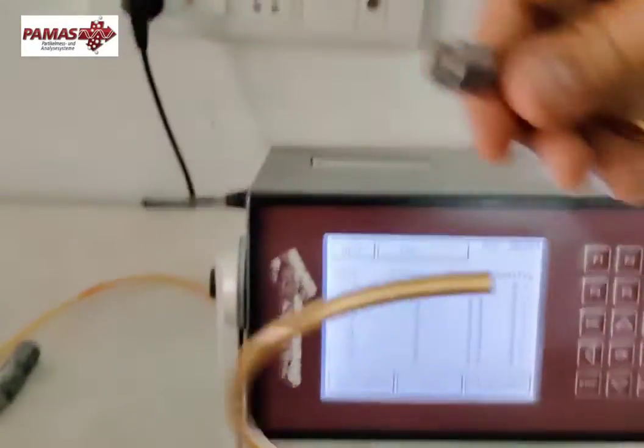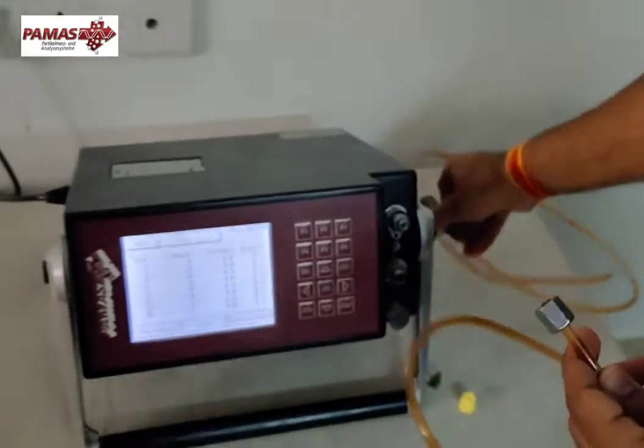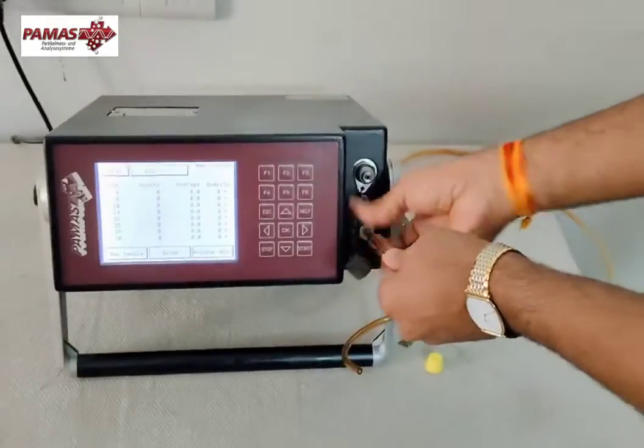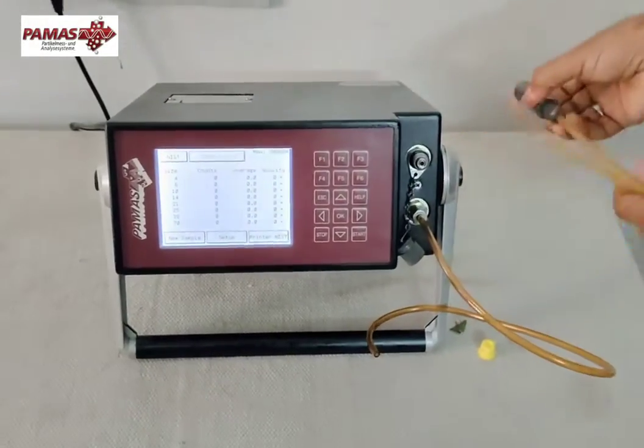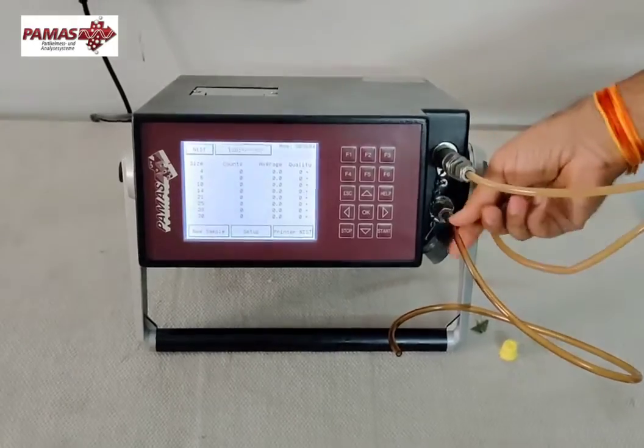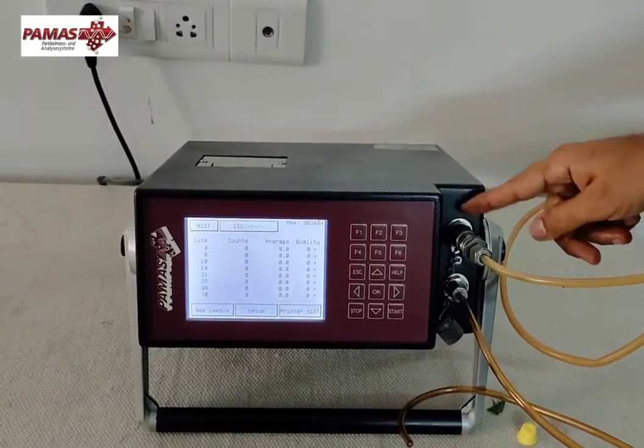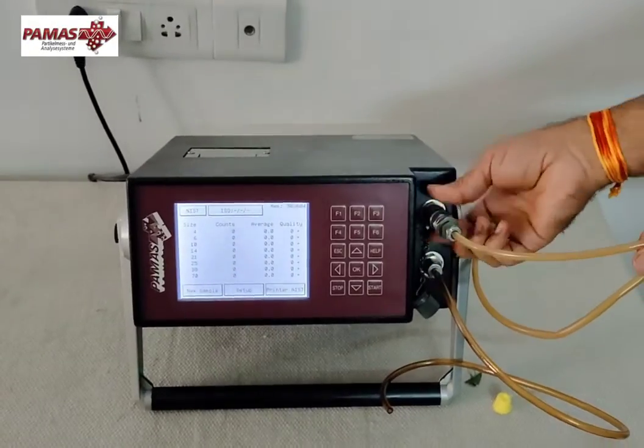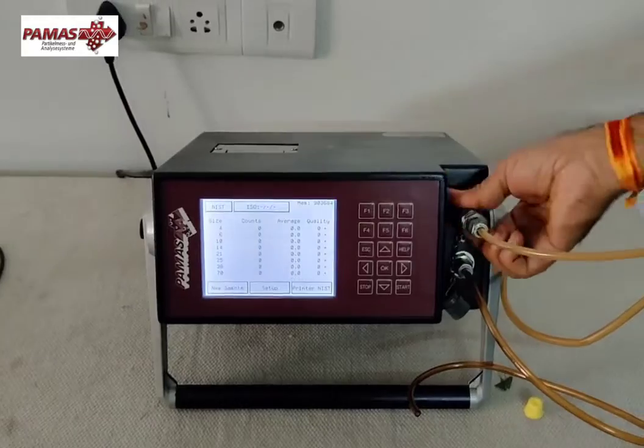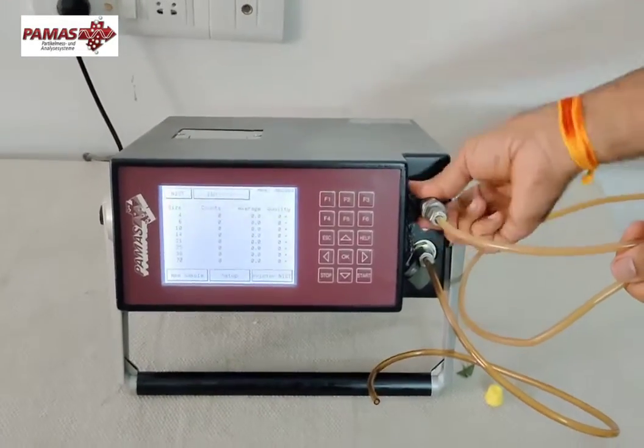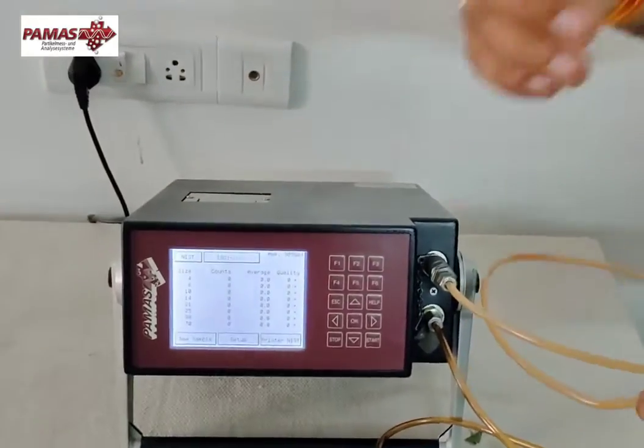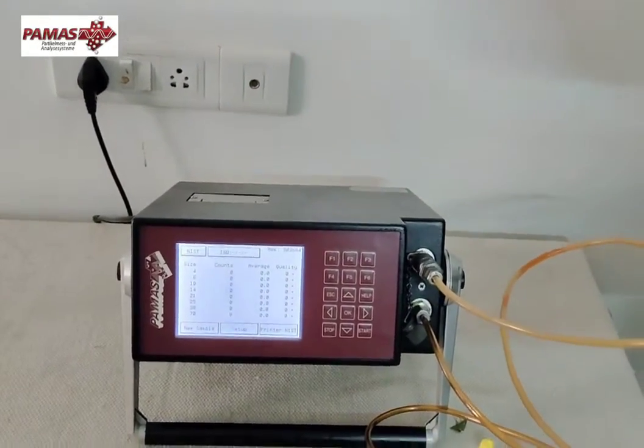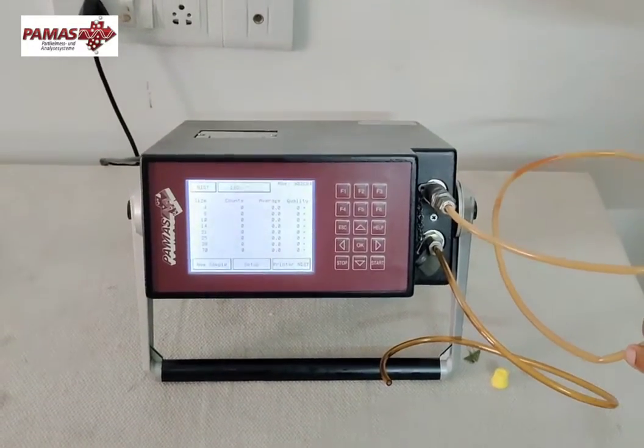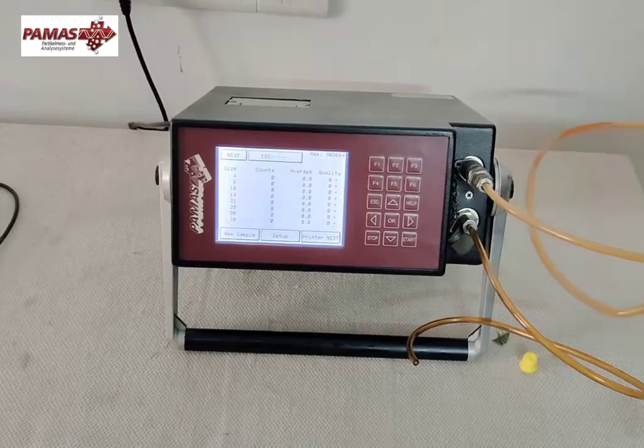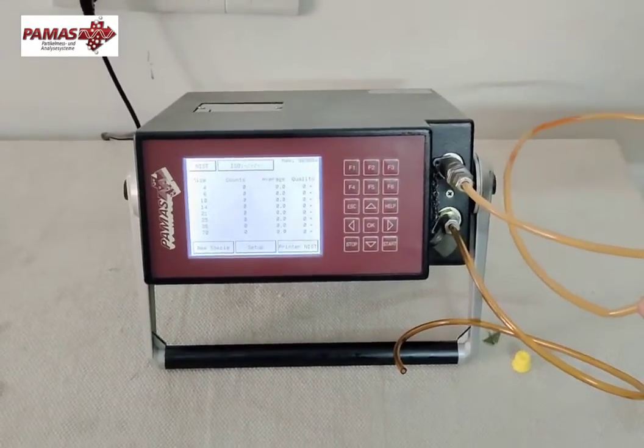So now I will show you how to make a measurement. We take these two hoses here and we will connect them to the low pressure input here. You just screw them in, and now we will connect this. When we are using offline mode, this is input, this is output. When we are using high pressure mode, this is input, this is output. It's very simple. To make a single measurement, you can decide what kind of sample you want to take, whether you want to measure 10 ml, 20 ml, 50 ml or 100 ml, and how many times you want to repeat that sample from the bottle.